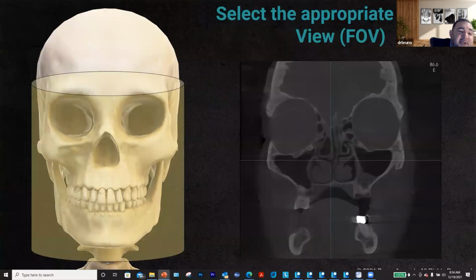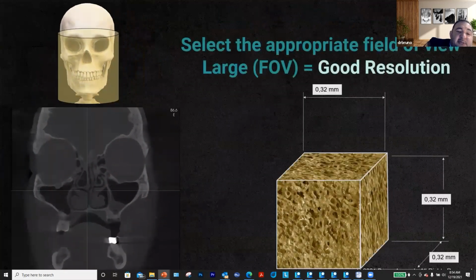And the reason for that is that every time I have a larger field of view, there are going to be some computational issues associated with the image. And it starts with voxel size. So with the larger field of view, I'm going to have larger voxels. Typically on the X800, when you're doing larger fields of view, your voxel size is 0.32, which means that you're at 0.32 millimeters, I'm sorry, for resolution.